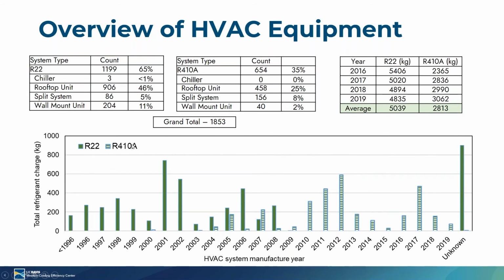If we look at all the equipment and the charge of that equipment, and then analyze by year, you can see, as we would expect, R22 was phased out January 1st, 2010. So you can see here that there's no R22 equipment manufactured after 2010. I should mention we got the manufacture year from the serial number of the equipment. And you can see here then the R410A equipment picked up. Because we're analyzing these last 4 years, the charge of the R22 equipment is dropping, right? Where we assume here that any R410A equipment replaced a piece of R22 equipment. So over the years, we estimate the R22 charge at the district from 2016 to 2019, and the same for the R410A, assuming that this new R410A equipment replaced R22 equipment.